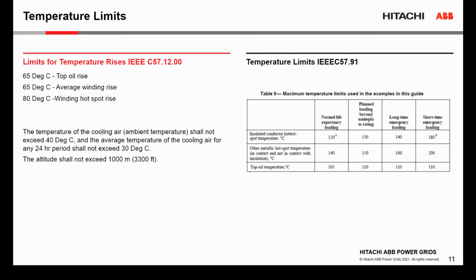We designed the transformer to meet the temperature limits for emergency loads, and during those events, the temperature limits are much higher. For long-time emergency loading, the temperature limit for the hotspot is 140 degrees C, and for short time, it's limited to 180. But at the same time, with much higher temperature, the aging of the transformer, the life expectancy of the transformer can be shorter, and at the same time, with much higher temperature, we may see some gases generated during those events.